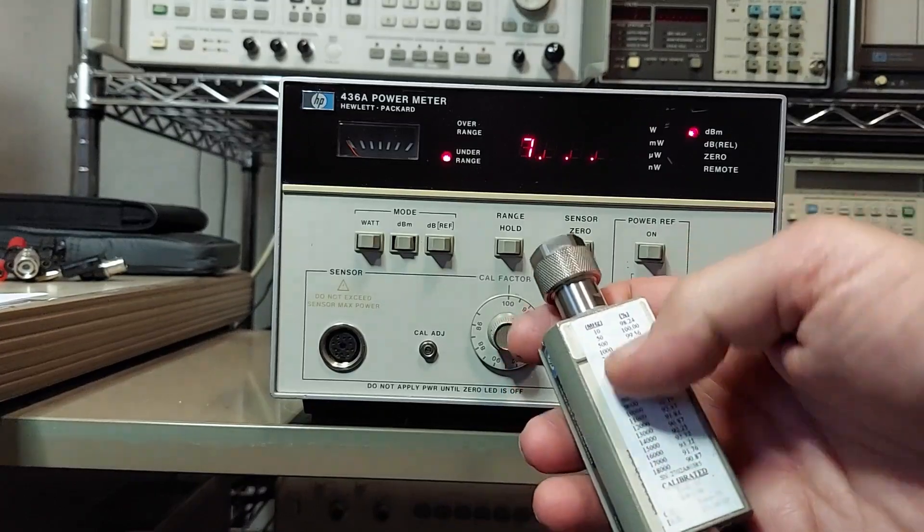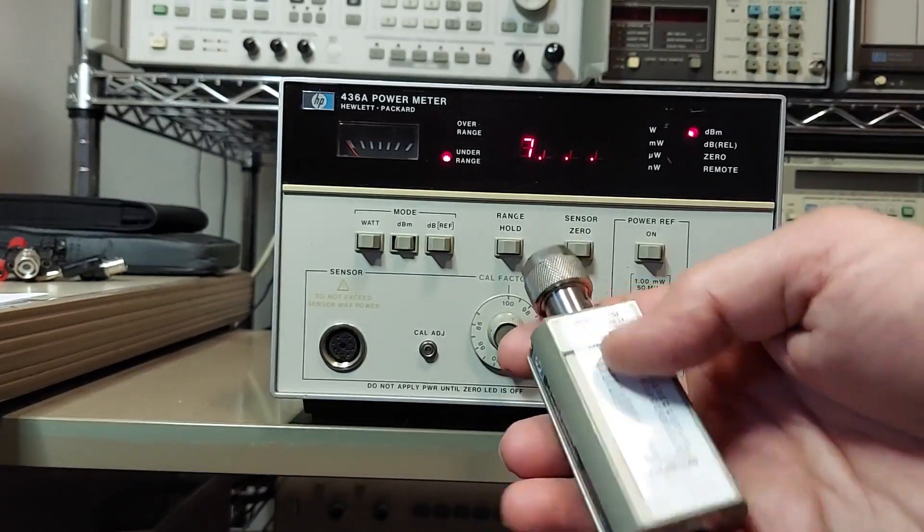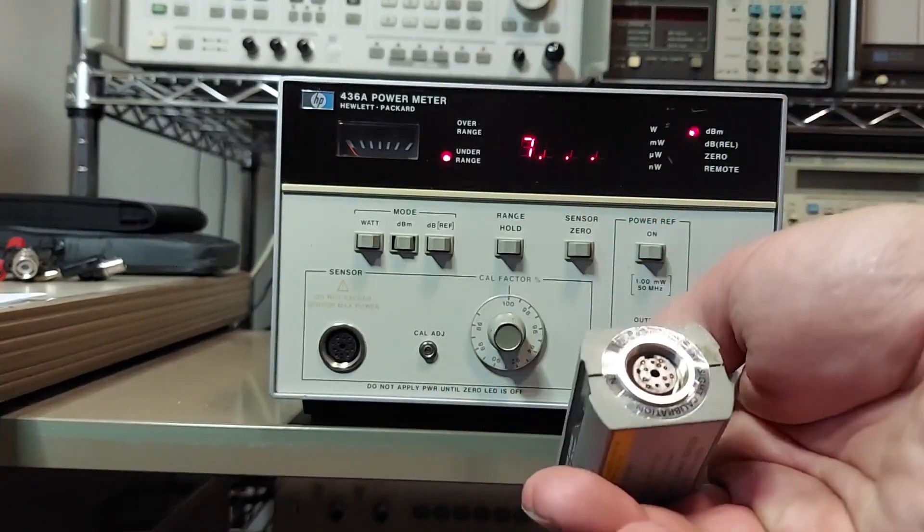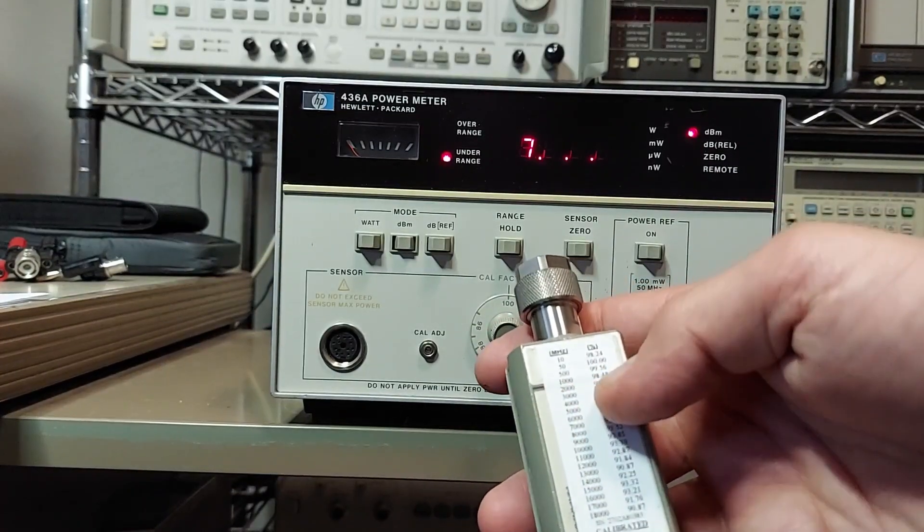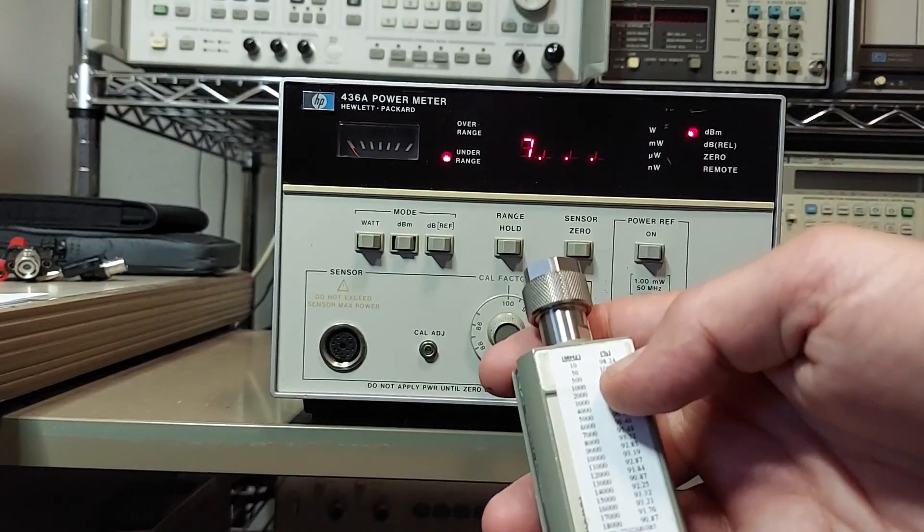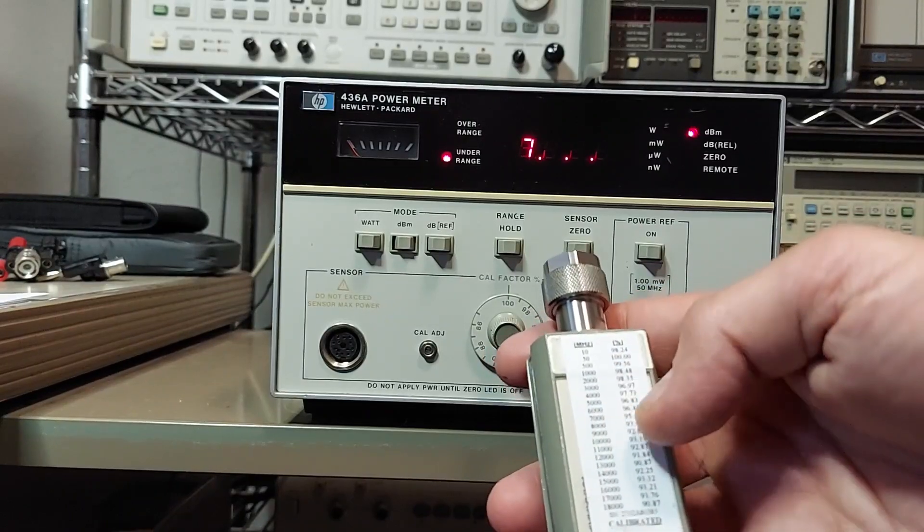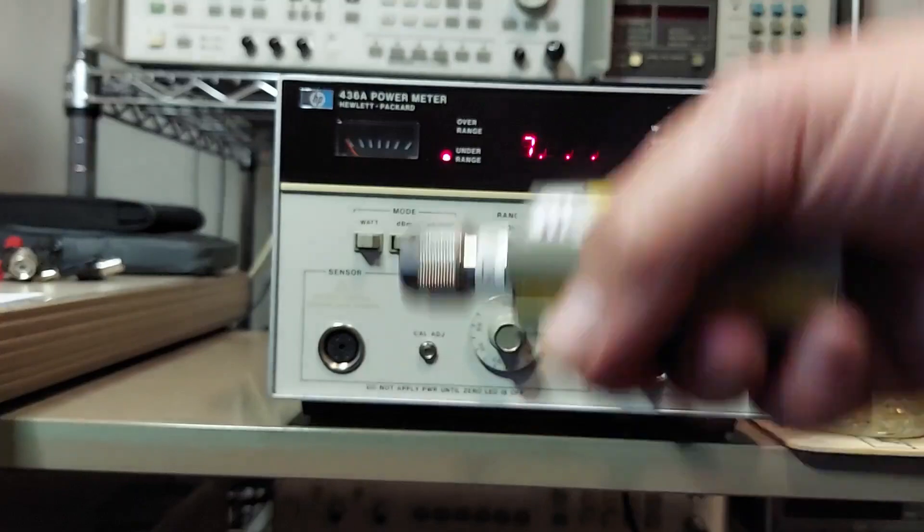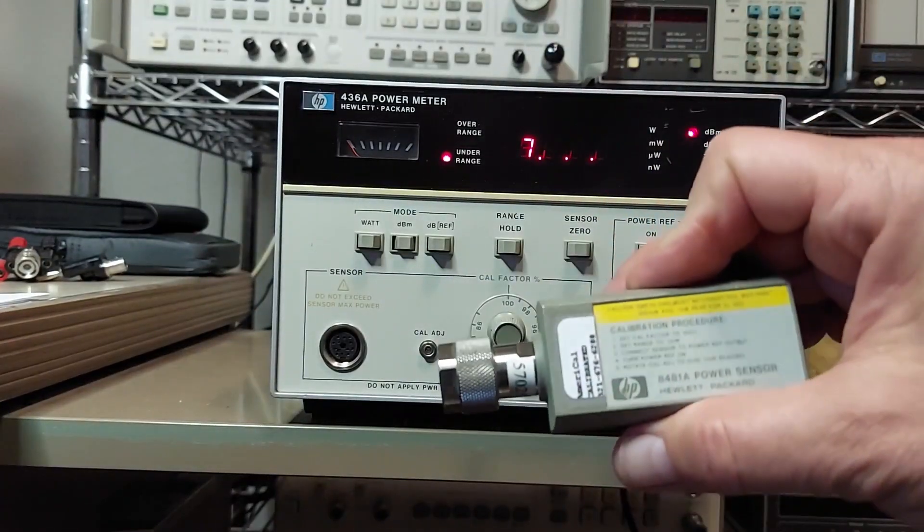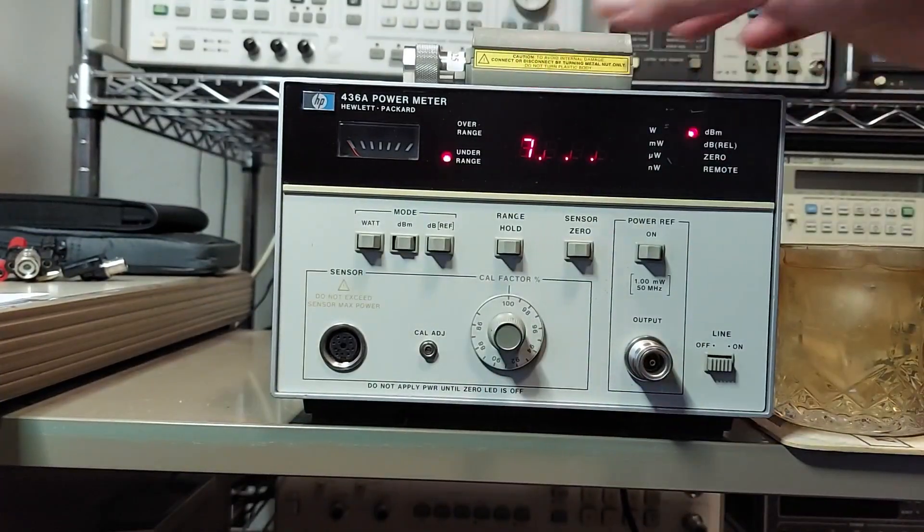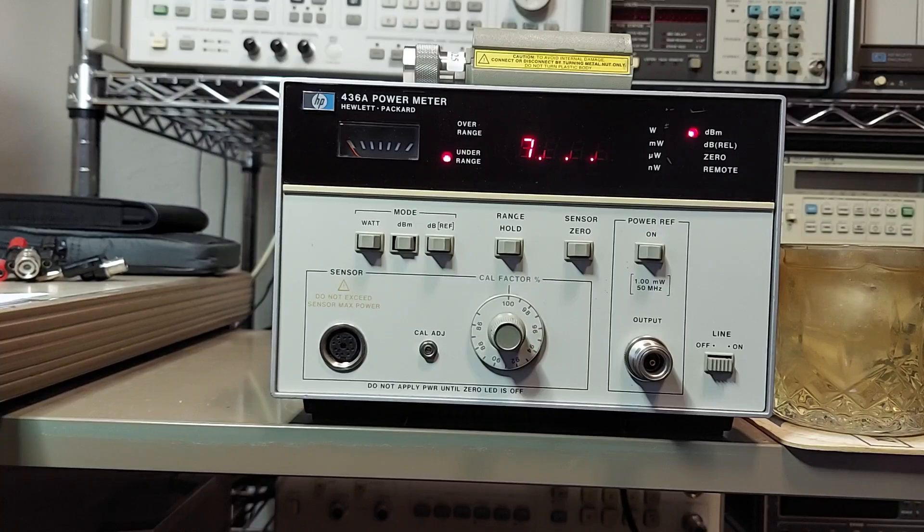Typically when you calibrate these, you want them on 100. This sensor here that was calibrated by Keysight, the calibration factor is 100 at 50 megs. So what I'll do is I'll hook this up and we'll go through a calibration routine.